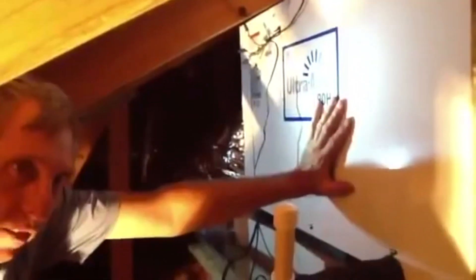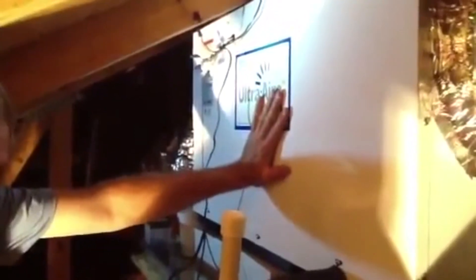This is the supply. This supply is going out to a mixing box in the back. And we've came out with two eights and put them in the highest part of the ceiling where the homeowners should not have really any issues with the extra heat. Because this moist latent air is coming from inside the house. It's dehumidifying the air out of it to 40% humidity is what we have to sit at.